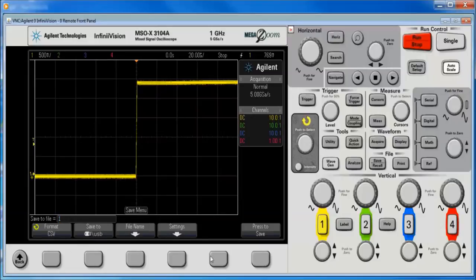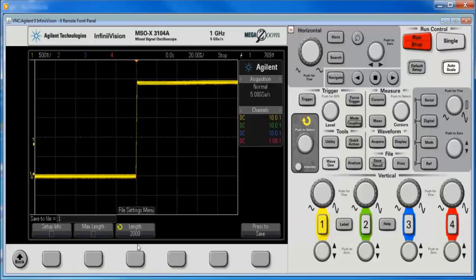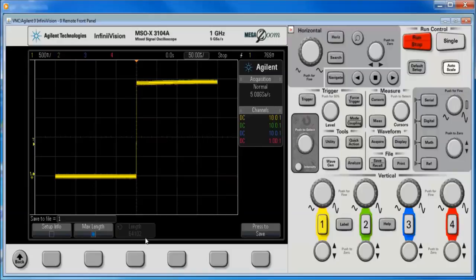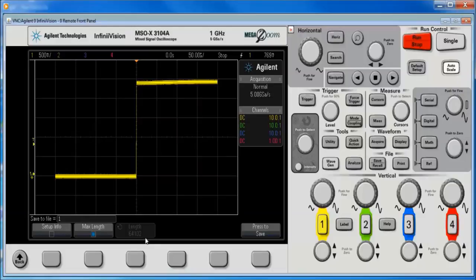So I'm going to go into settings and I want to select max length. Notice it went to 62.5. Why did I only get 62,500 points? Well, if I bring the data on screen I can get a little bit more. However, the CSV format only represents the pixels that are currently hit.